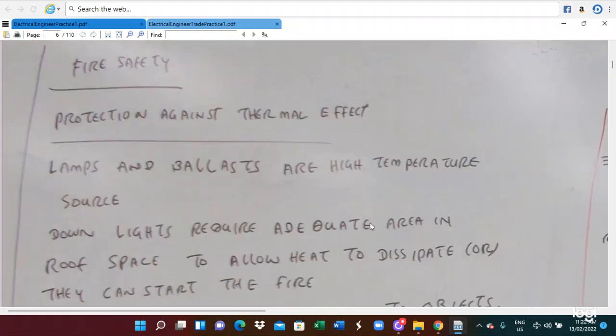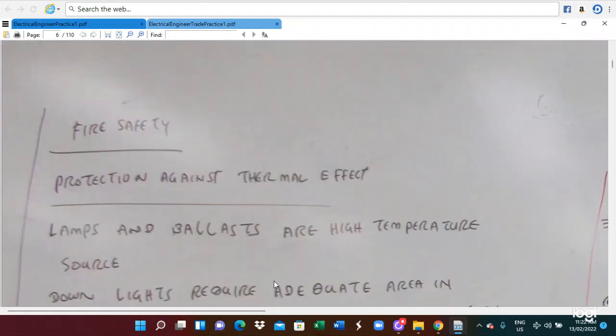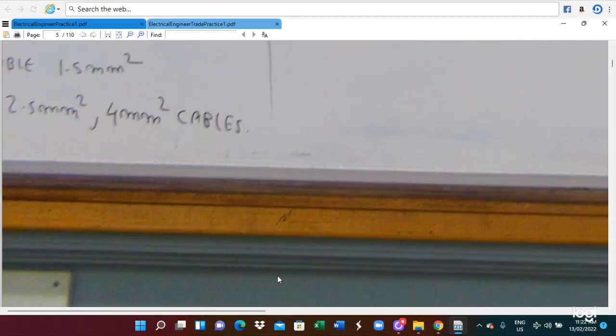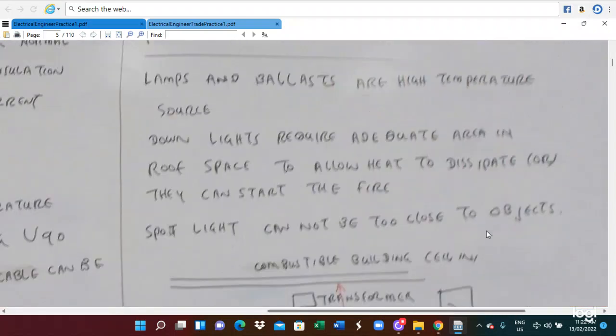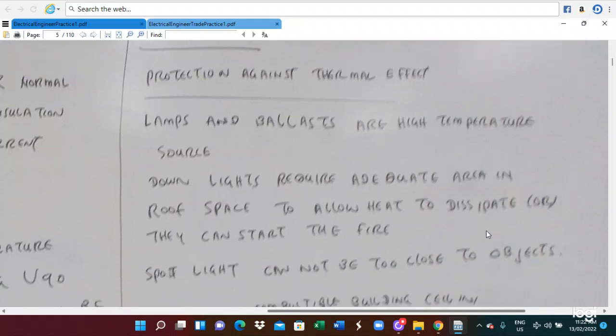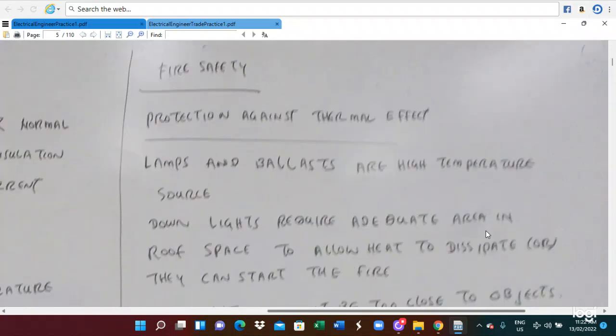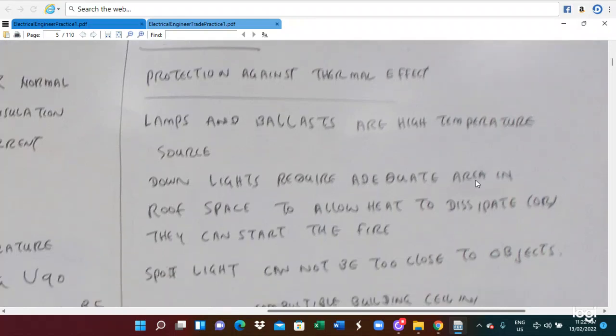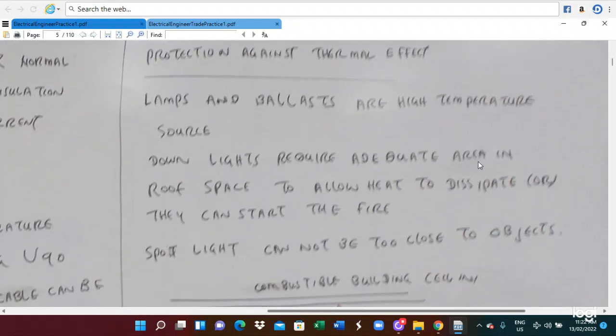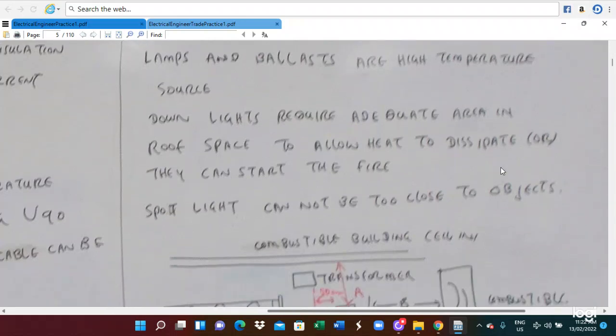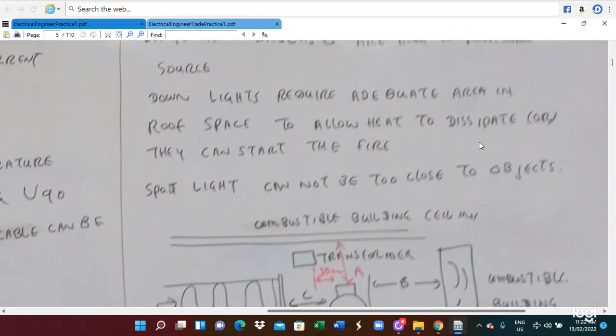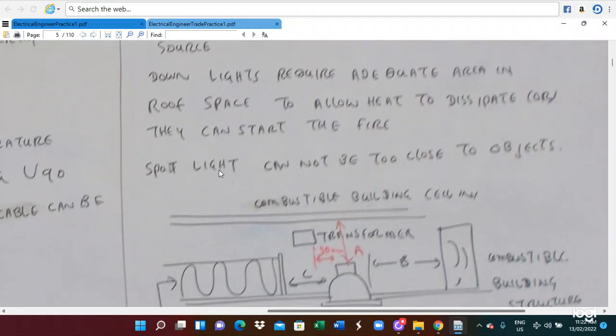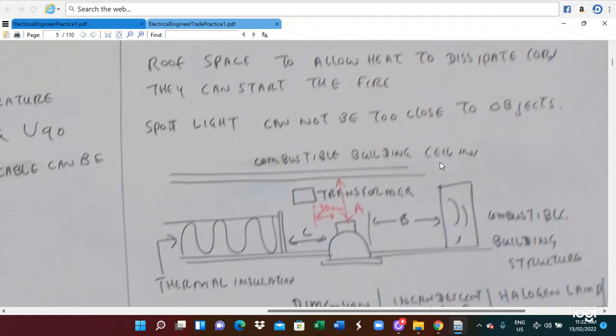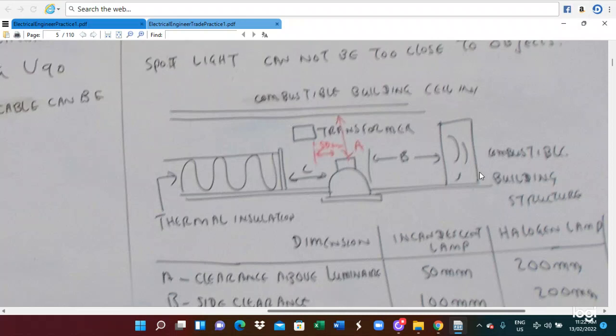Another thing is that we also have to provide fire safety. We have to protect against thermal effects. Lamps and ballasts are high temperature sources, so downlights require an air circulation area in the roof space to allow the heat to dissipate, or otherwise they can start a fire. A spotlight cannot be too close to an object. So this is for the ceiling, appropriate ceiling size.